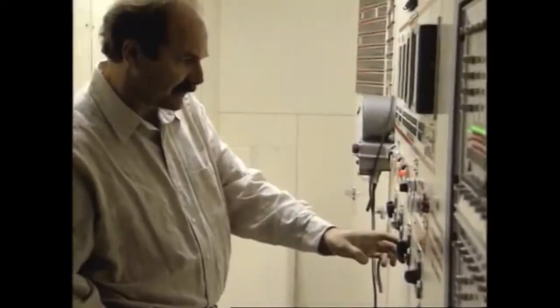If the lift station inspections indicate that the wet well levels are fluctuating too much or that the pumps are starting and stopping too frequently, then changes to the pump start and stop cycles need to be made. Install a continuous flow recorder for several weeks. Analyze the daily flow cycles and then try to adjust the different pump start and stop cycles so that the pumps can operate as continuously as possible.